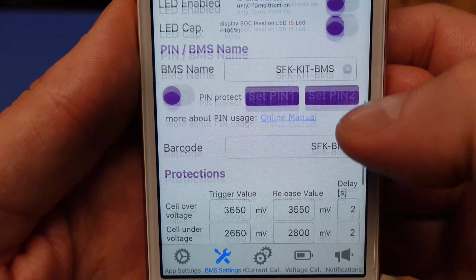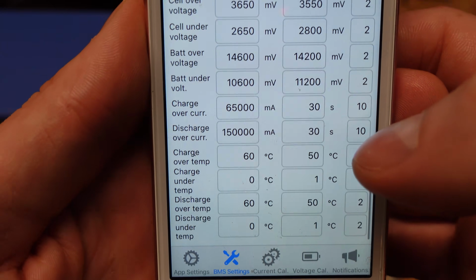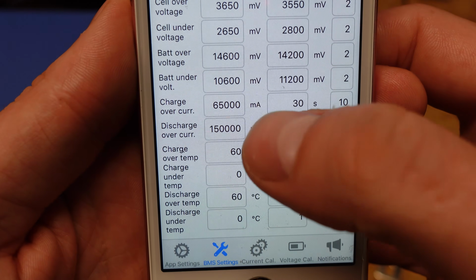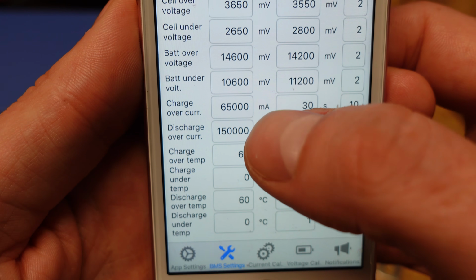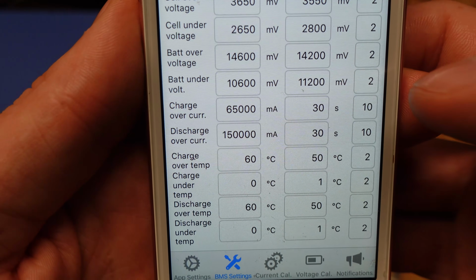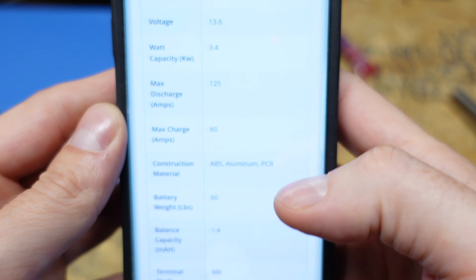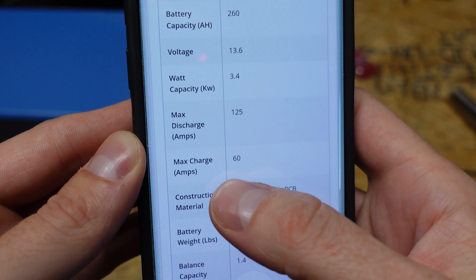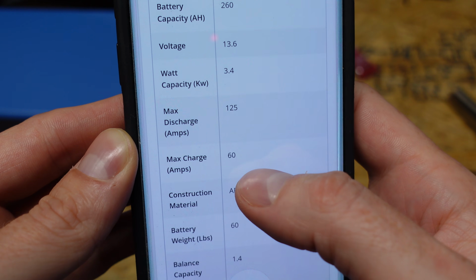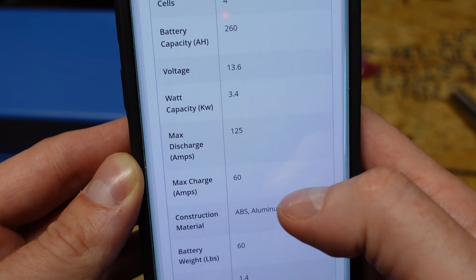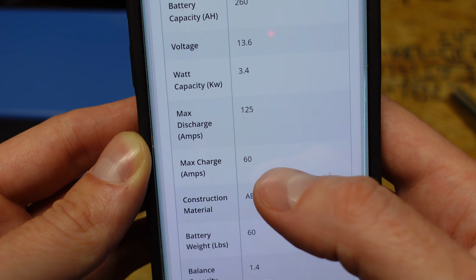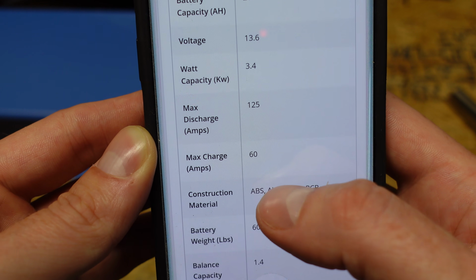So I'm going to pause here and go back to the documentation on the website to check what it says regarding the maximum charge current. I did find that it says max charging amps is 60 and max discharge amps is 125. So I don't know why they have this set for 60 amps on a 260 amp hour battery.